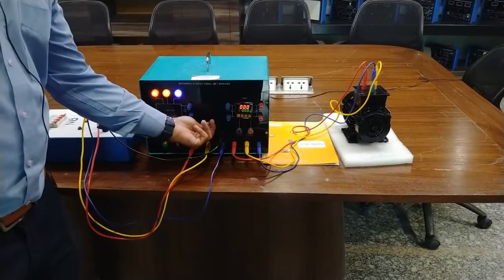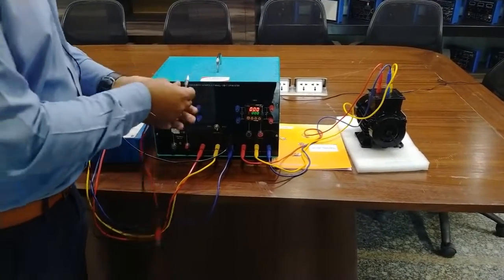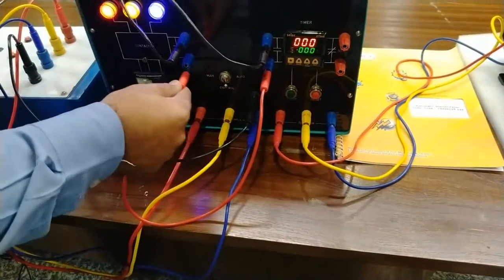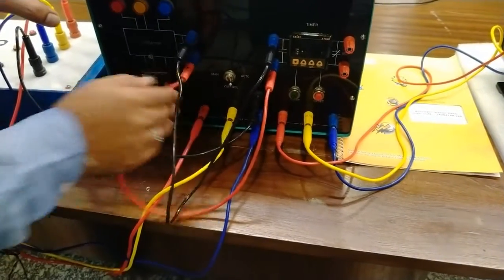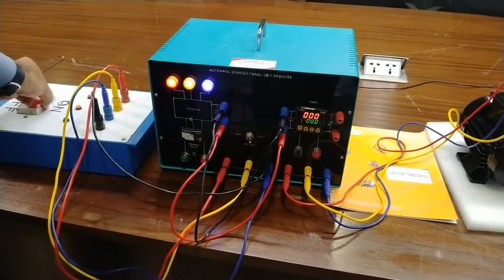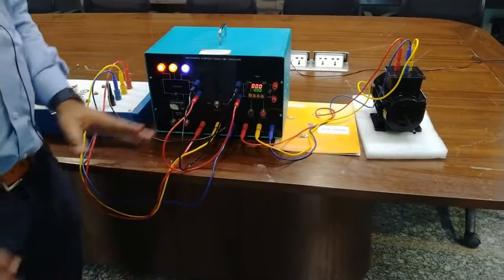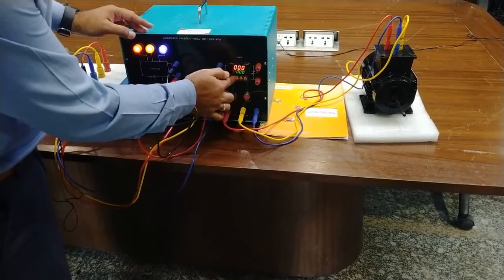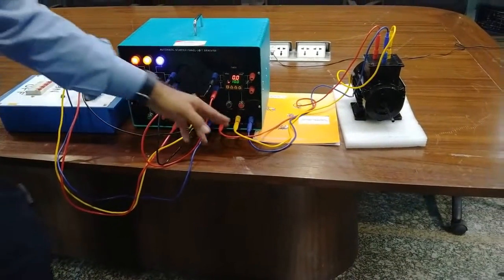Now we will do the automatic controlling of this motor. For this we will turn the switch to auto mode. We require two patch cords to connect the NO terminal of the timer to the NO terminal of the contactor. Before this, turn off the three-phase supply for safety purposes. Now we have turned off the supply and made the connections. Now we will again turn on the supply and set the timer as per our requirement to control the motor. We will set it to 10 seconds. The timer has been set to 10 seconds.